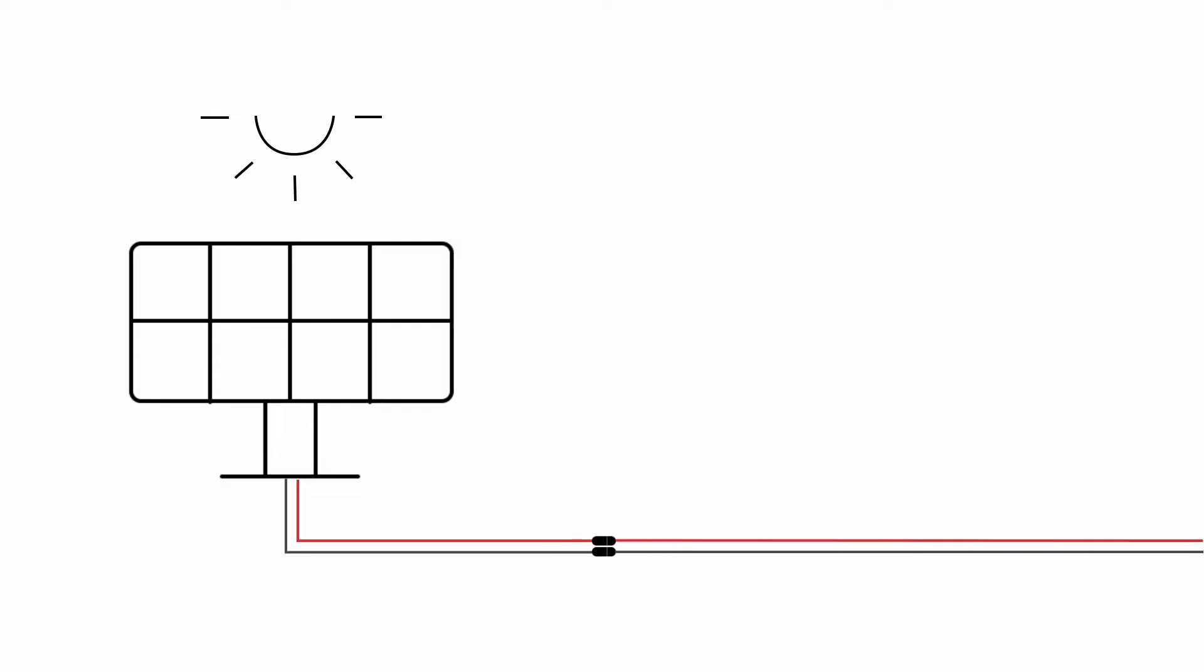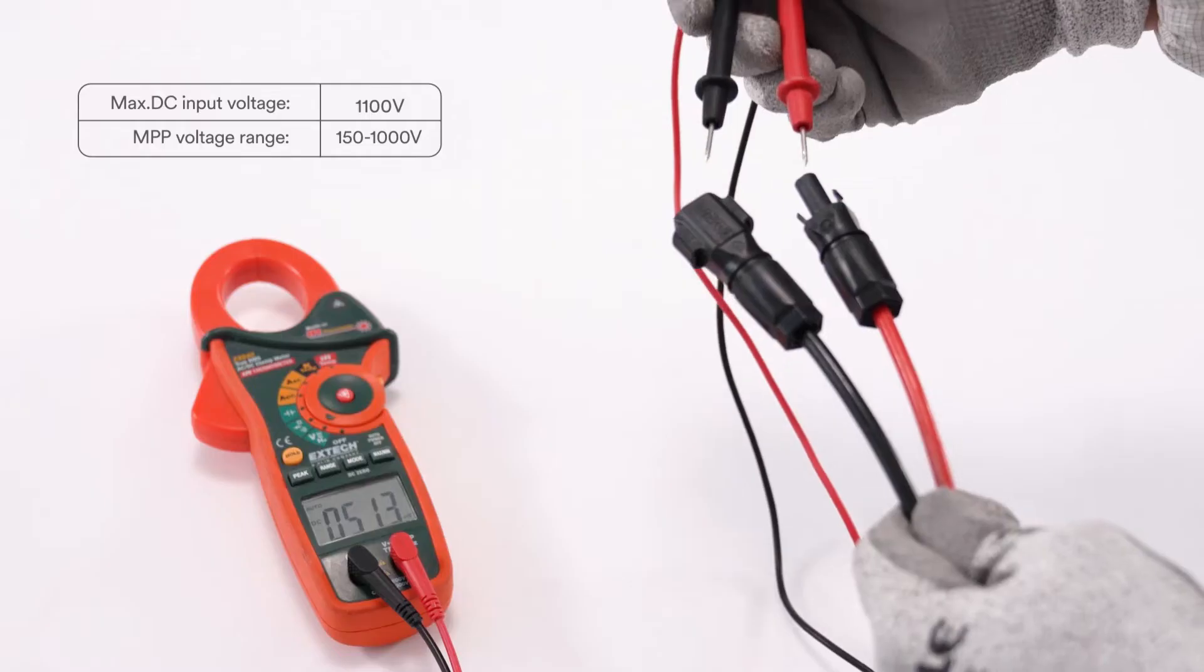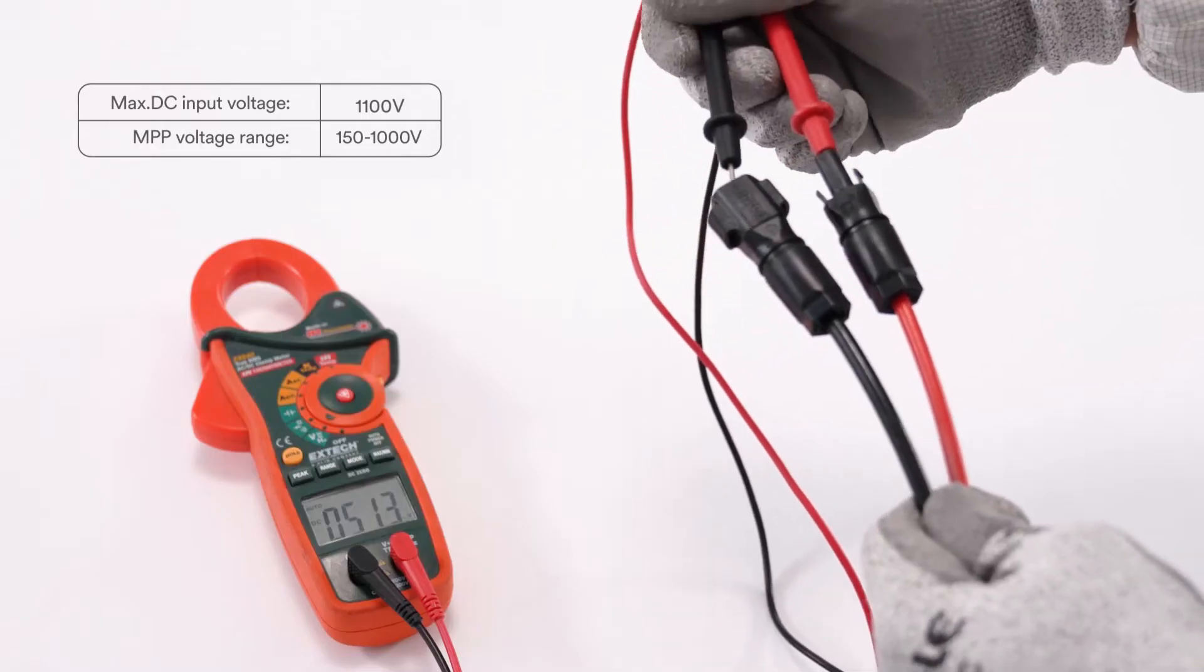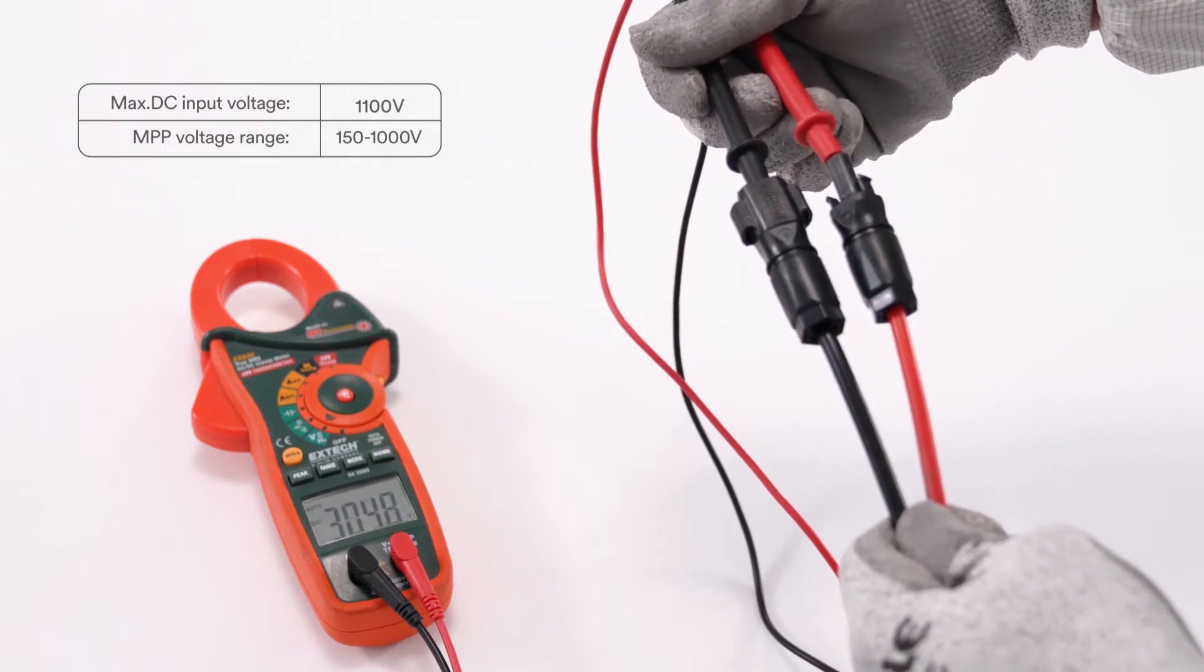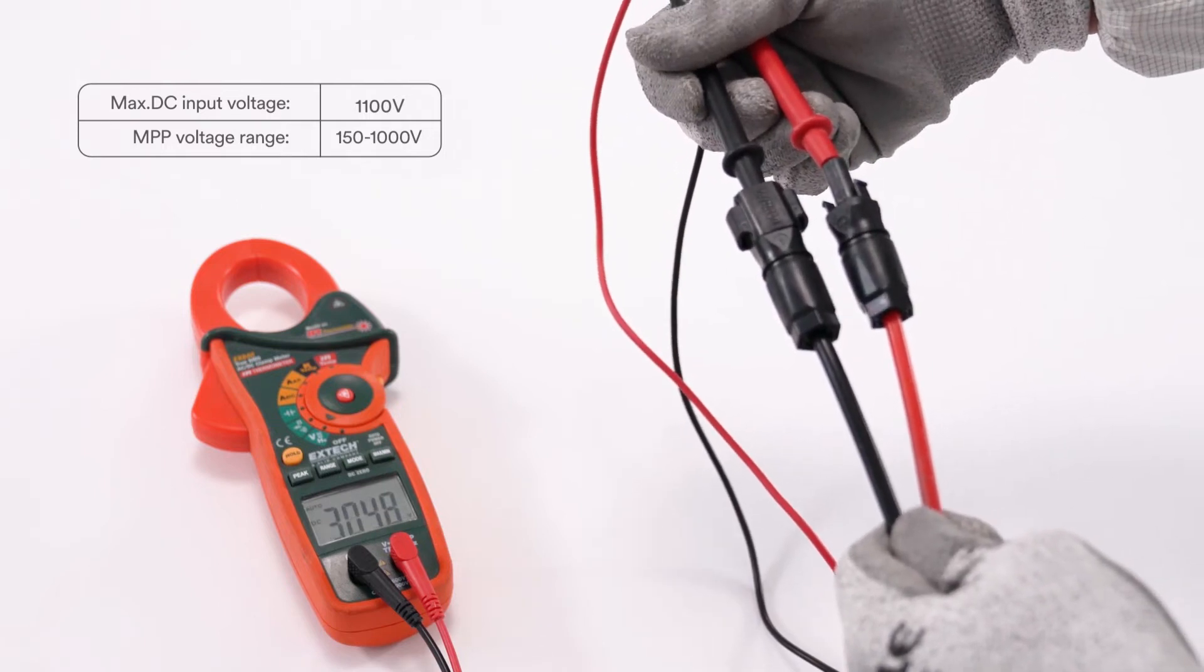Connecting the PV array. Check whether the DC connector has the correct polarity. Ensure that the open circuit voltage of the PV array does not exceed the maximum DC input voltage of the inverter.